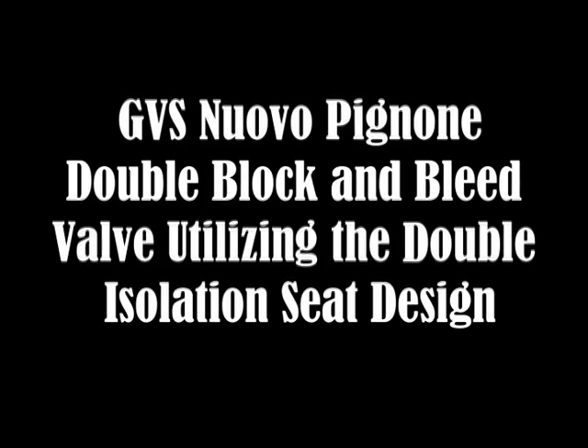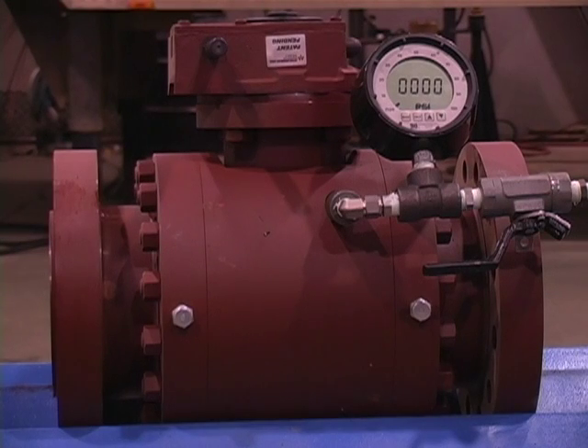In this first test, which is typically called an inside out test, you see an ANSI class 600 GVS Nuovo Pignone valve set up with pressure in the body cavity. The pressure represents the maximum test pressure as outlined by API 6D and CSA Z245.15. As you can see when a leak test is used with a soap and water unit, there are no bubbles, which proves there is no leakage.